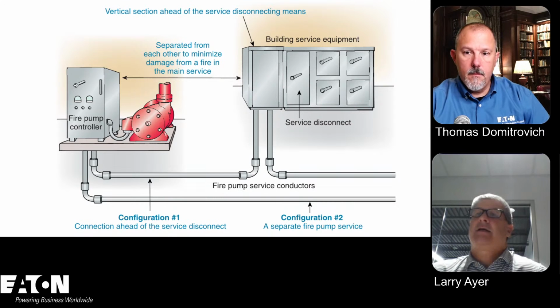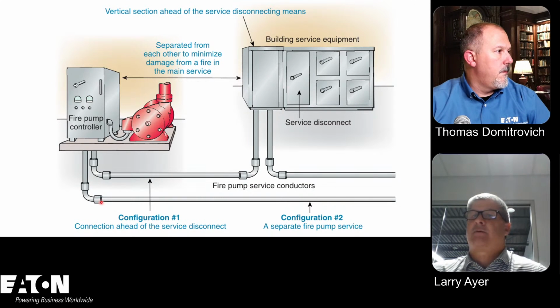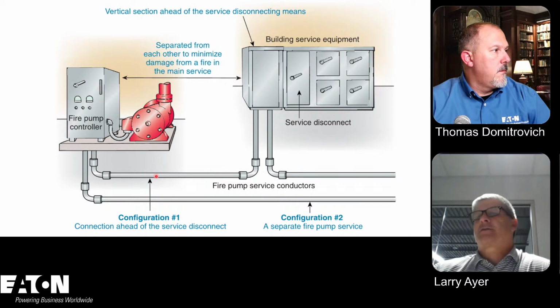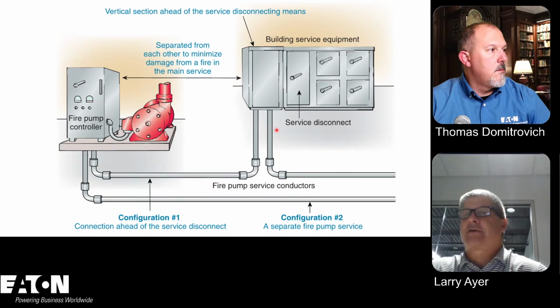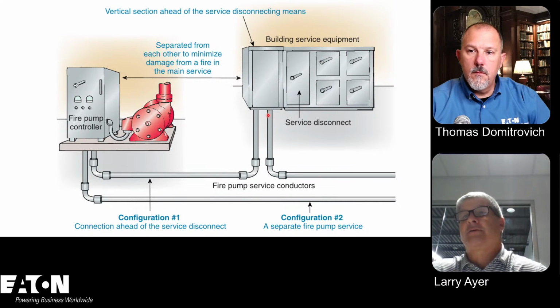They tap off on the load side of the metering cabinet, right? So most of the time, all the time, the utility still wants the fire pump meter, even though the fire pump is never used. We don't want it to be used, of course, because we know that's a hazardous condition if something's really happening in the building and we're using that. But you tap off there, and then you go to the fire pump controller.